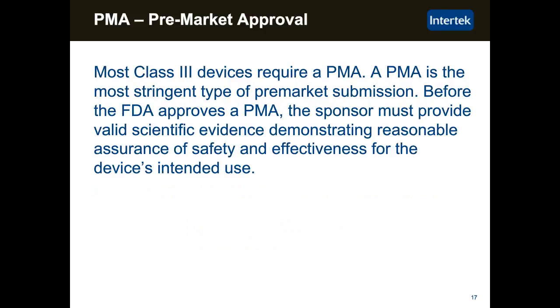Now let's talk about the pre-market approval. Most Class 3 devices require a PMA. A PMA is the most stringent type of submission. Before the FDA approves the PMA, the sponsor must provide valid scientific evidence that demonstrates reasonable assurance of safety and effectiveness for the device's intended use. When we talk about valid scientific evidence, in the case of a PMA Class 3 device, that's usually going to mean clinical evaluations run under controls with a protocol, and that data will all then be submitted to the FDA to demonstrate safety and effectiveness.